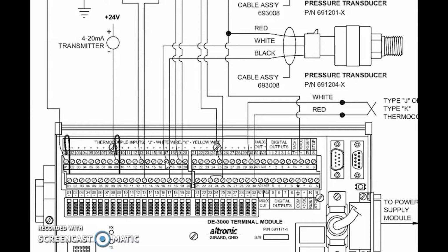The ground wire puts a permanent load on the pressure transducer, so that as the actual pressures change and the variable signal voltage changes, we have a completed circuit with the black wire to put a load onto that circuit. If the ground wire connection becomes jeopardized, or a weak ground, or a lot of positive backfeeding voltage comes in from some transient stray source, that can actually make the reading go high.